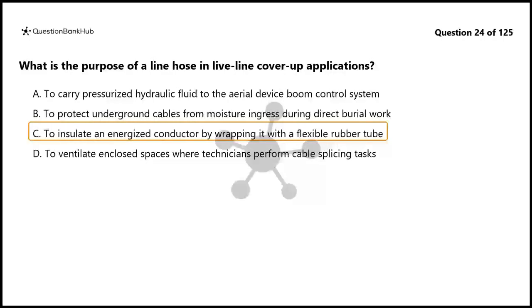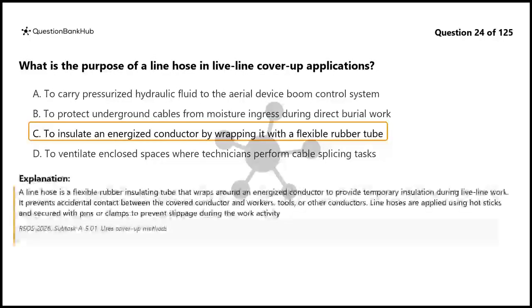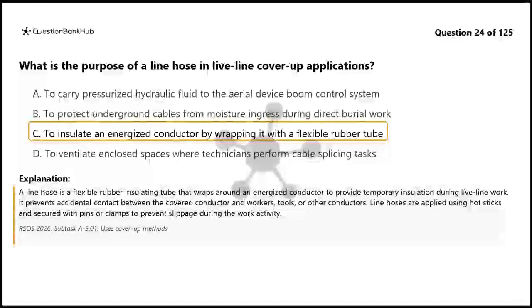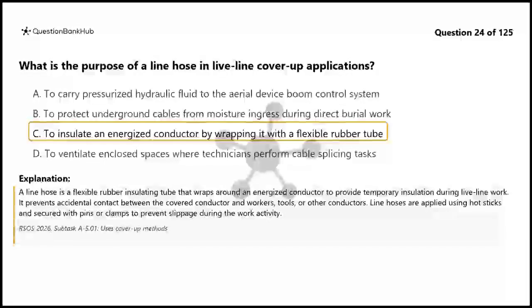The correct answer is C. A line hose is a flexible rubber insulating tube that wraps around an energized conductor to provide temporary insulation during live line work. It prevents accidental contact between the covered conductor and workers, tools, or other conductors. Line hoses are applied using hot sticks and secured with pins or clamps to prevent slippage during the work activity.